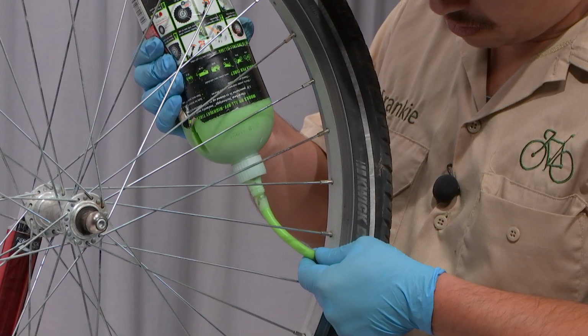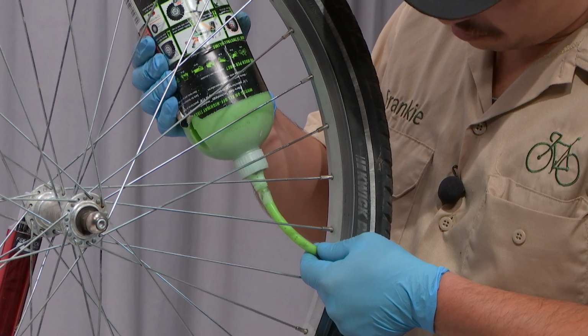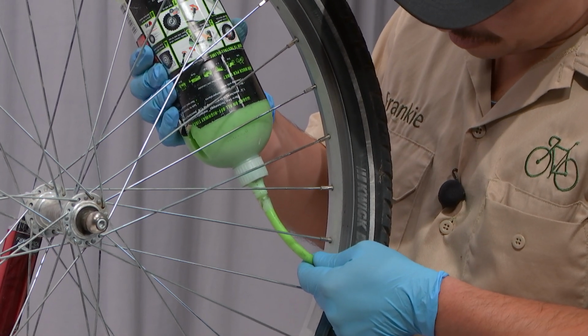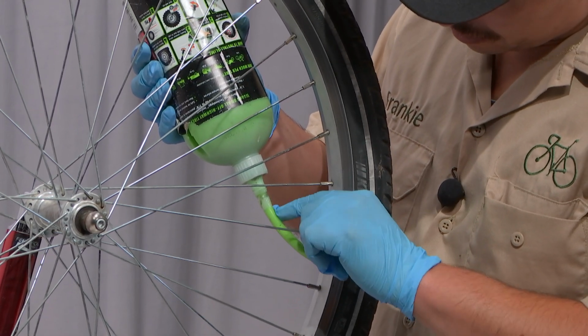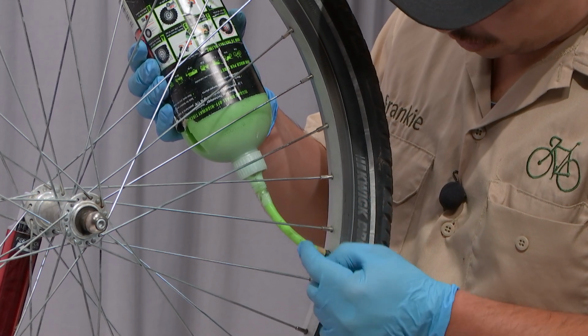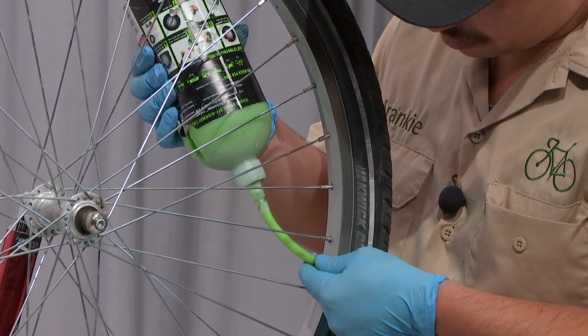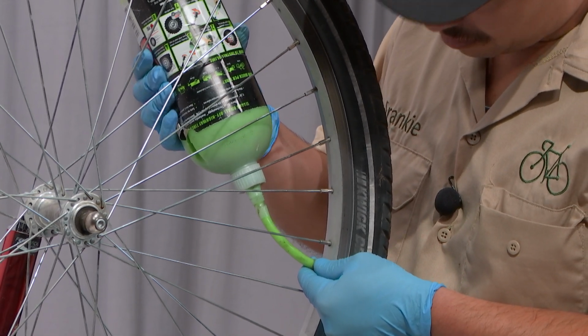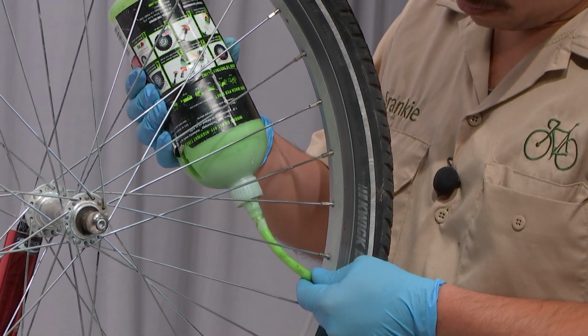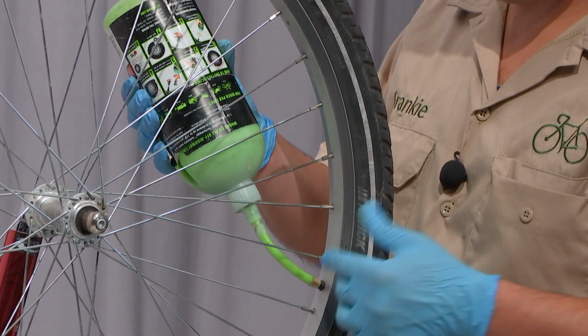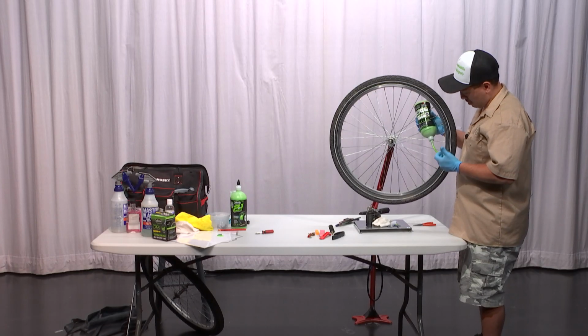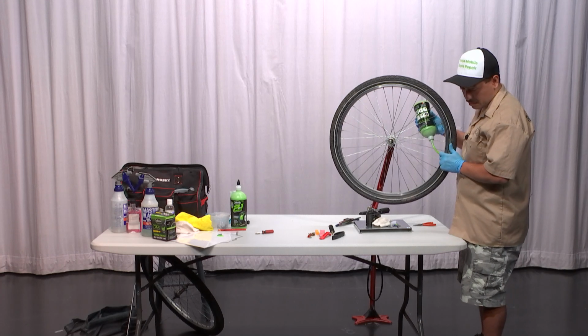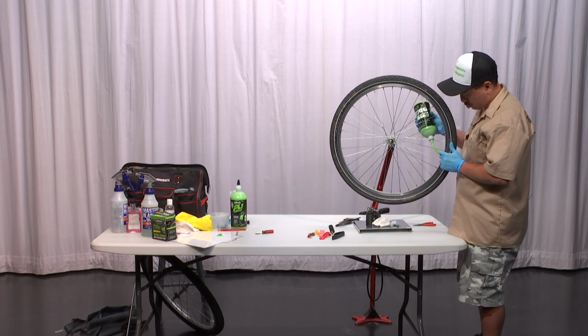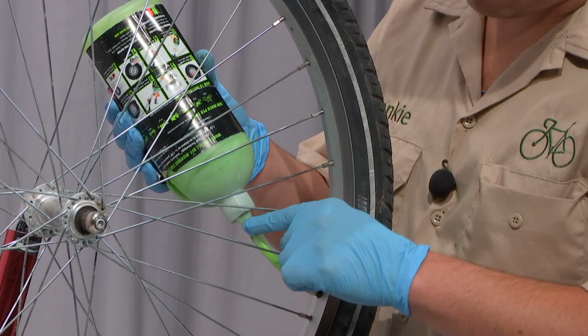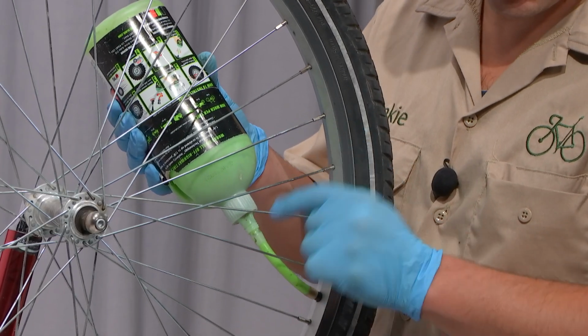Then I squeeze, and you can see it flowing. Do this in a well-lit area - there are little black dots or beads in the slime, so you can see it flowing. I don't want to put too much in there, but if it becomes difficult, it may be clogged. The fibrous material may have clogged the Schrader valve, or it can clog the nozzle on the cap.